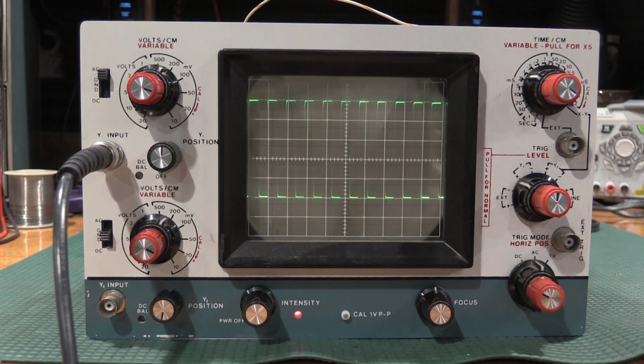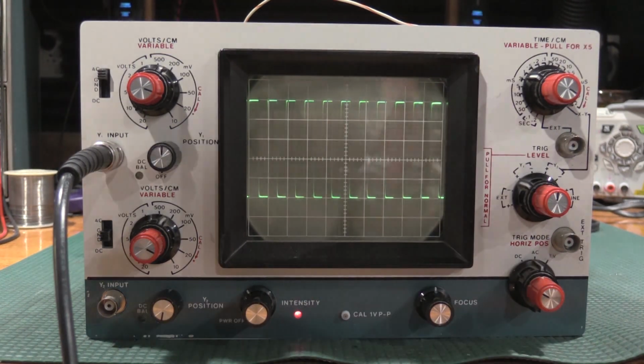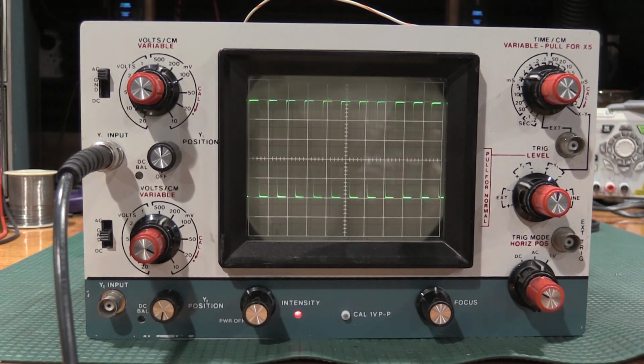Okay, I've got the scope queued up to do the calibration measurements. The calibration on this one's going to be quite short. There are far less adjustments in this particular scope than there are in a Tek scope. So the first one is the vertical amplifier. We do the adjustment on the 200 millivolt range. I have it set up now and comparing it with my PG506, the calibration generator.